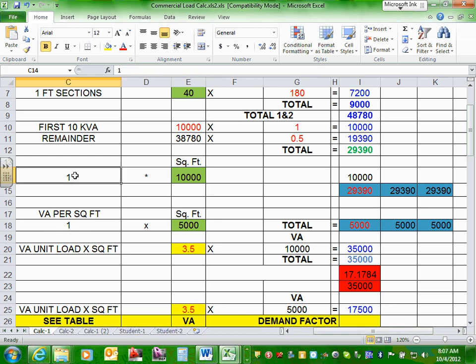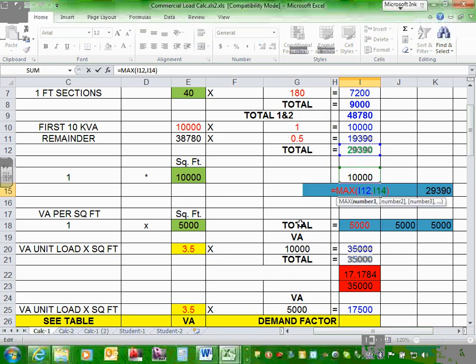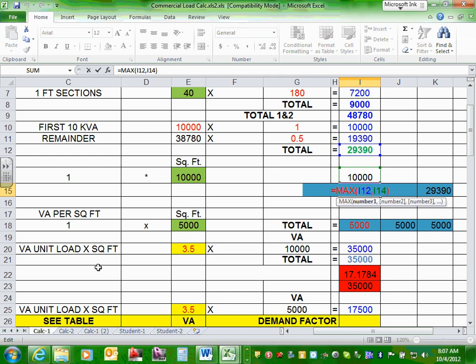I have 10,000 square feet for the building multiplied by 1 VA/sqft, giving 10,000. Then I pick the MAX of these two numbers using the Excel MAX function: MAX(cell1, cell2). This picks the largest of the two because that's what the code requires for office buildings. In your application, the max might actually be the 29,000 — it depends on your numbers.